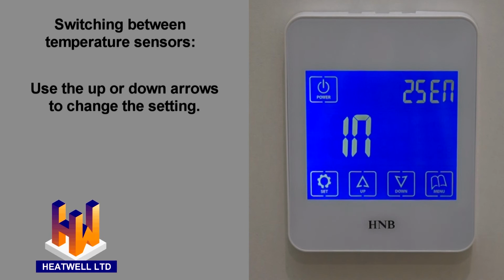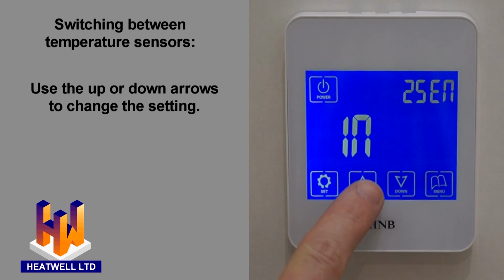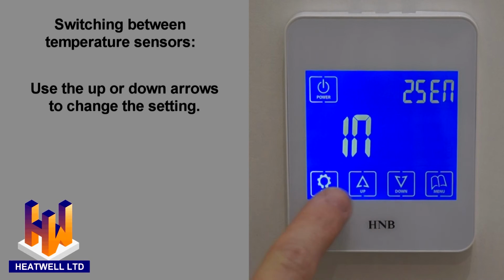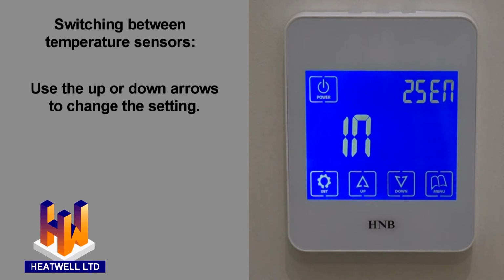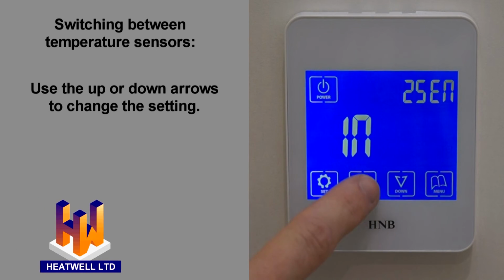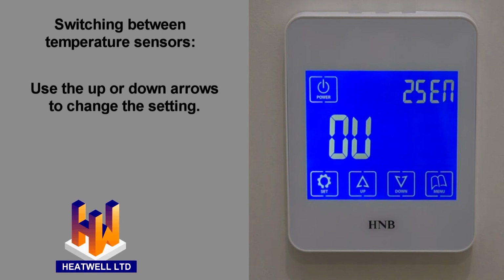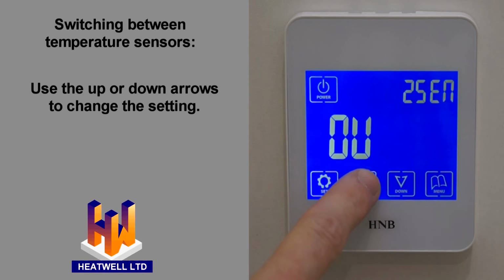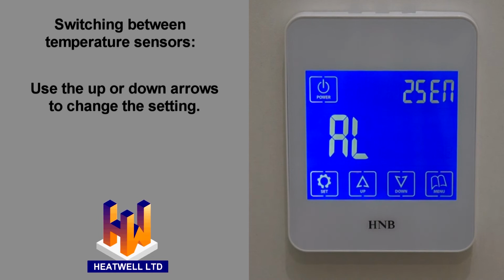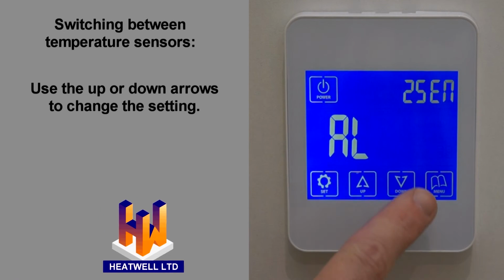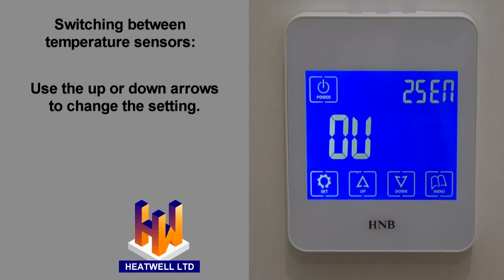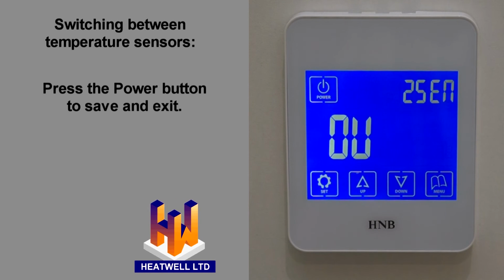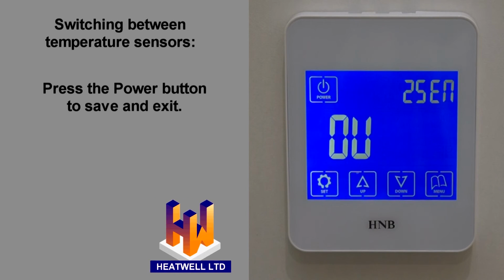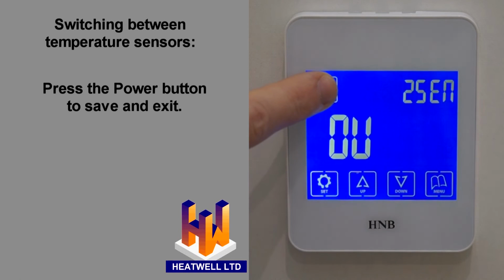Use the up or down arrows to select your preferred temperature sensor. IN means the unit will use its internal temperature sensor. OU means the unit will use its outer or floor temperature sensor. And AL means the unit will use all its temperature sensors. In this case, we'll select the floor temperature sensor. Once you've made your selection, press the power button to save and exit.